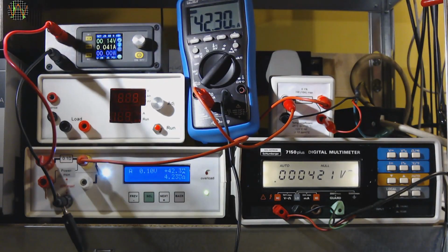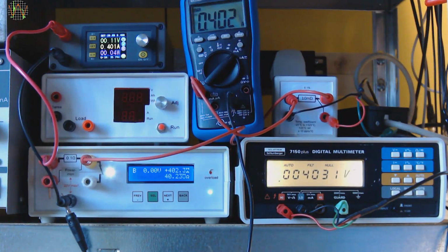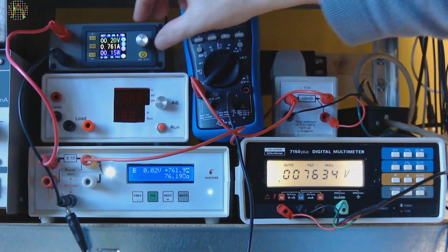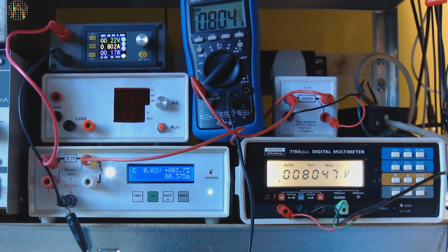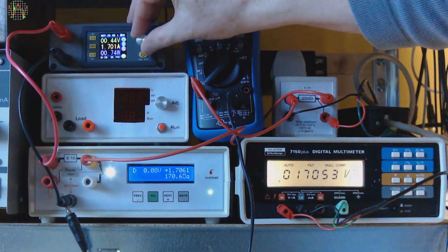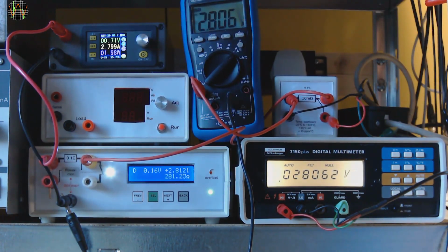In this test I'm testing range A as shown by the A in the upper left of the PowerMon LCD. I'm increasing the current from 20 milliamps to 400 milliamps in 20 milliamp steps. Continuing the test in range B from 400 milliamps to 800 milliamps in 20 milliamp increments. The BM235 is now in the amp setting. And continuing in range C from 800 milliamps to 1.6 amps, this time in 50 milliamp steps. The last range D from 1.6 amps to 3.2 amps in 100 milliamp steps. As designed, overflow is shown when exceeding 3.2 amps.